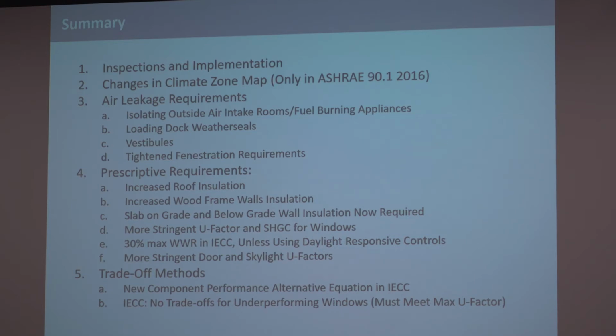The climate zone map is changing in ASHRAE 2016 only, but stay tuned and check what happens when Pennsylvania and Philadelphia adopt to find out what happens to various counties, especially surrounding Pennsylvania, in the climate zones. The air leakage requirements are much more stringent: isolating those outdoor air intakes, loading dock weather seals, tighter vestibule requirements and fenestration requirements.